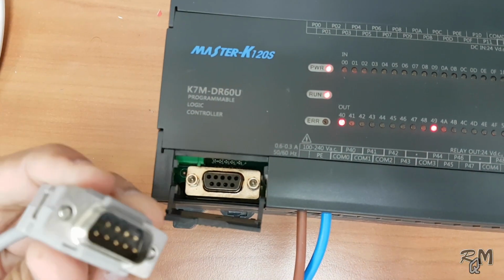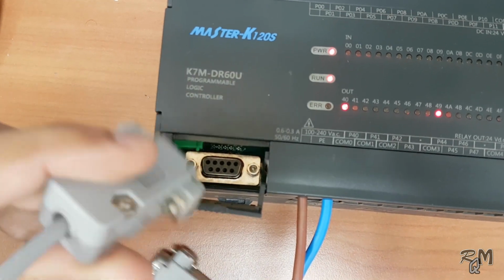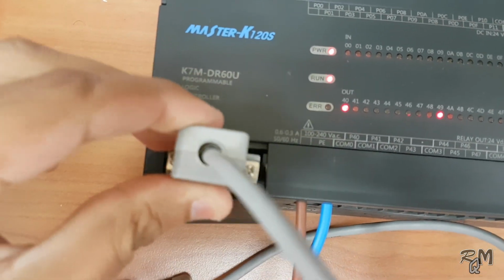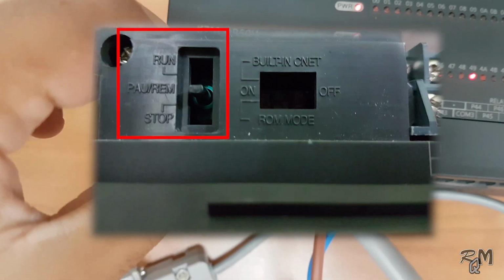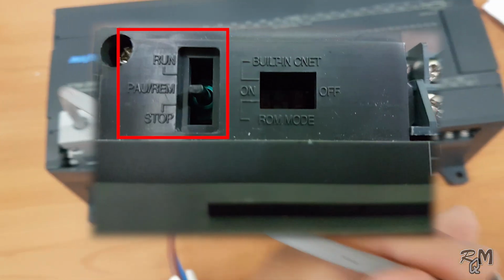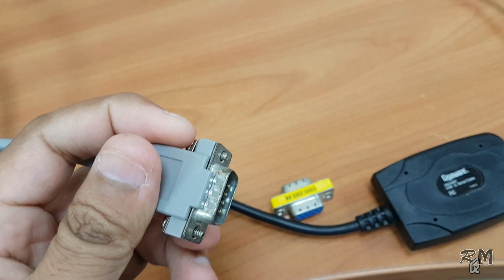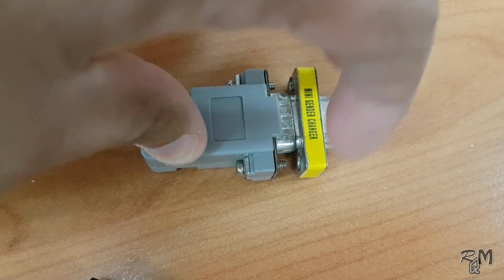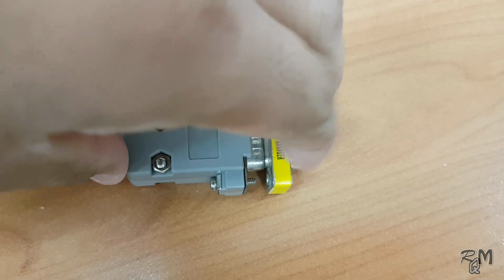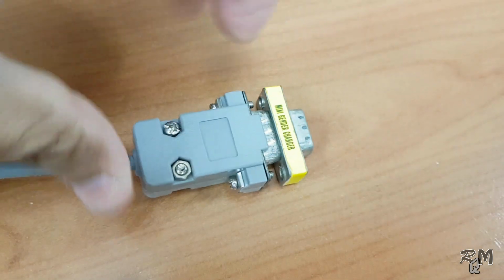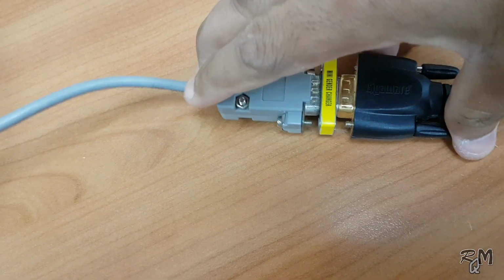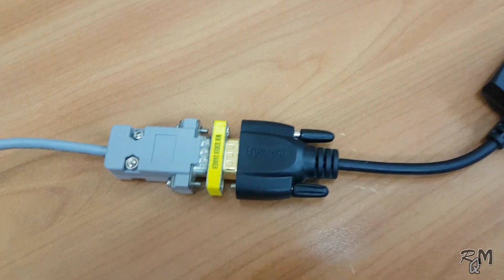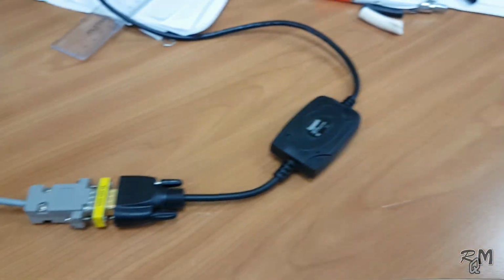Okay, now connect the RS232 communication cable to the RS232 port of the PLC. Make sure the PLC is powered on and the selector switch is at the center where PAU/REM is written, which is program mode. Here I have a straight RS232 cable and I'm using a mini gender changer to convert it to a cross RS232 cable. I don't have a serial port in my programming laptop, so I'm using a USB to serial adapter for communication.